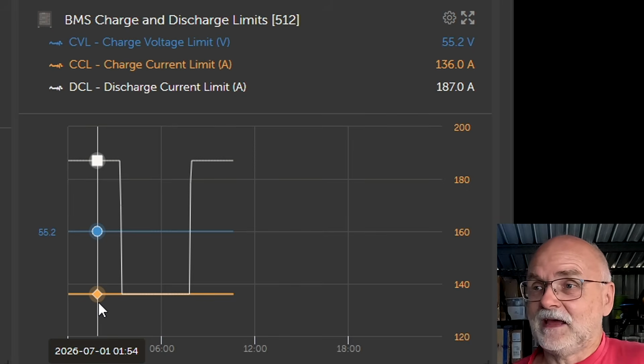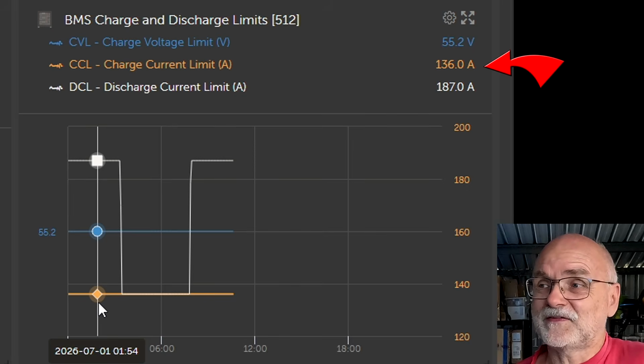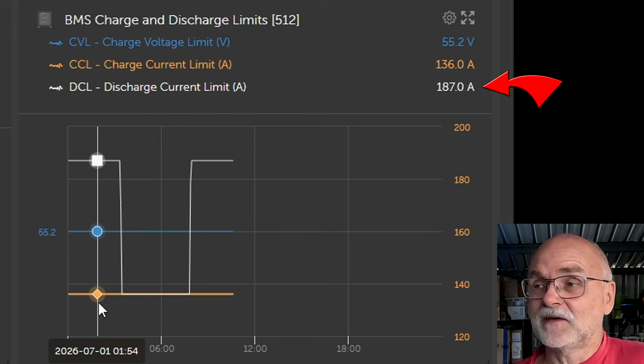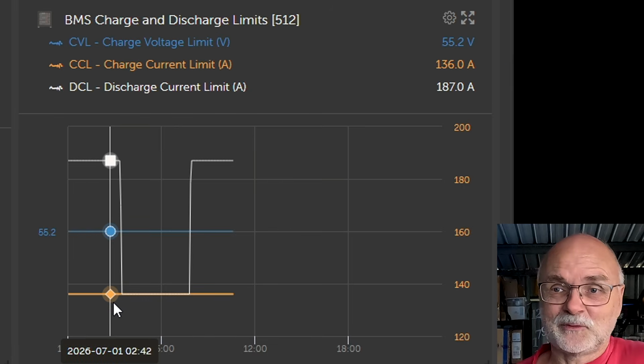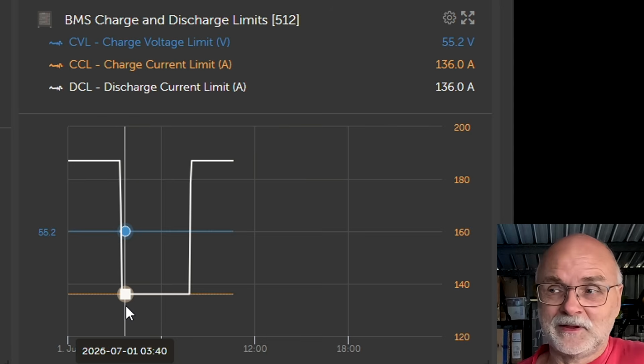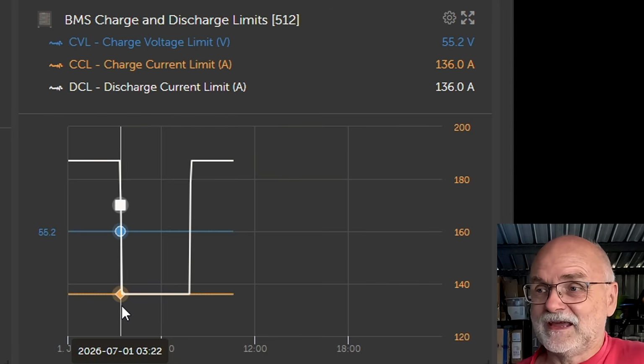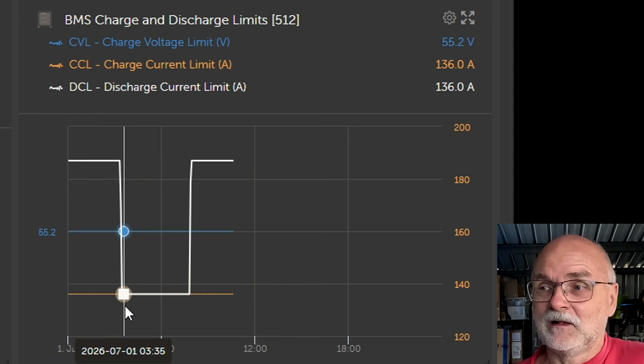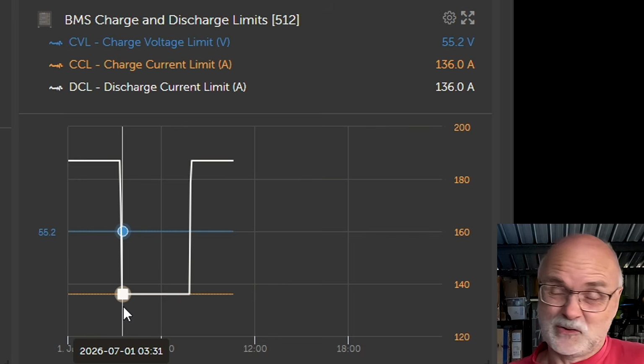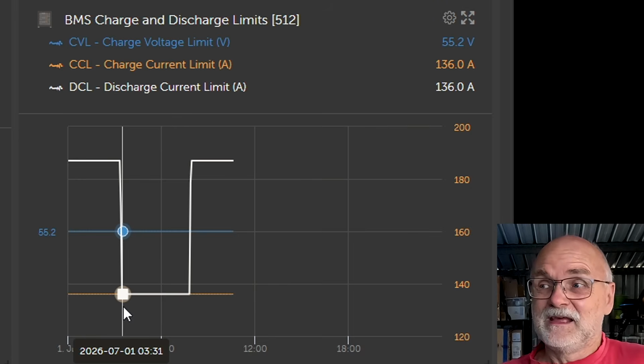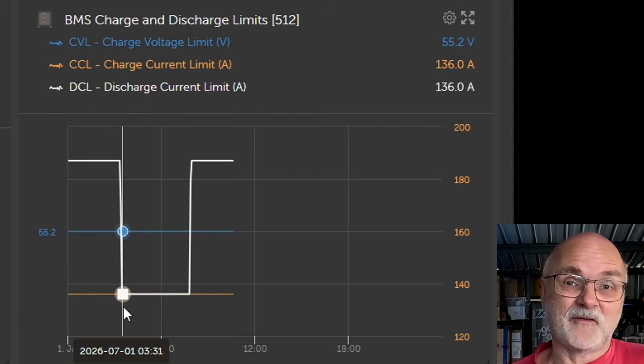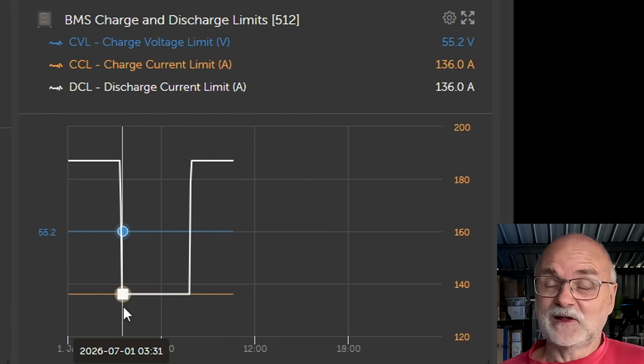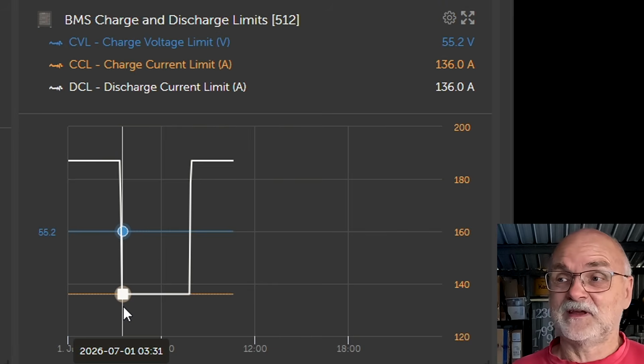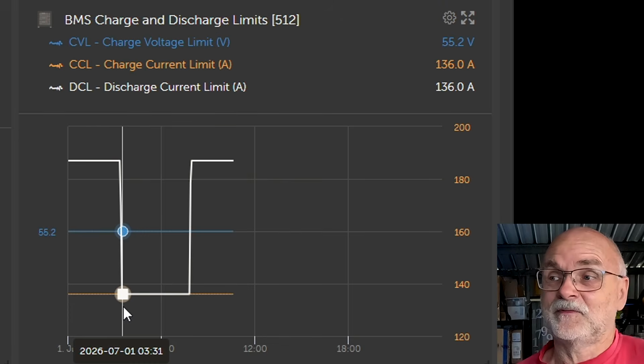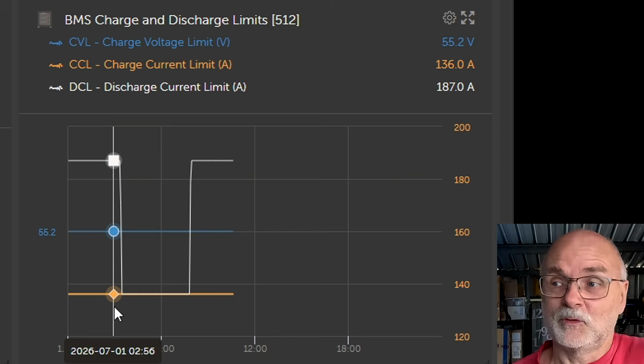And when we have a look at the CCL and DCL of the system, it's 136 amps for charging and 187 amps for discharging. When this happened with cell number 3 in the middle shelf battery, and the BMS turned off, it automatically reduced the DCL, the available discharge current from the system. Not that it affects me because I'm off-grid here, but if you were grid connected, it tells the inverter, hey, use less power from the battery because one of them has turned off. So it calculates only with the 2 remaining batteries and tells the inverter you can pull only 136 amps instead of 187, what it was before.